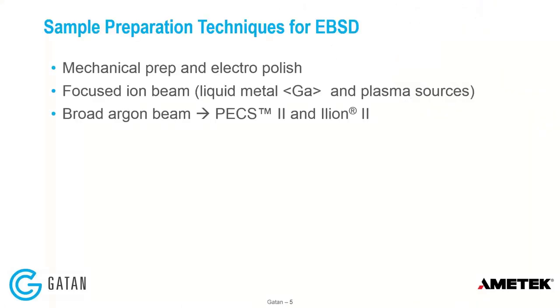There are multiple ways to prepare samples for EBSD. The traditional and probably most widely used is mechanical prep, maybe followed by electropolish. Recently, in the last five to ten years, people have been using focused ion beam — originally gallium FIBs, and now more recently plasma FIBs — mostly for 3D EBSD. And finally, broad argon beam, which could also be called broad ion beam because it is possible to use other ions besides argon. In the case of Gatan, we have two products, a PECS II and an ILION II, that can be used for preparing samples for EBSD. And I view sample prep as requiring a complete toolbox of a variety of tools, because no single tool will do everything you need.